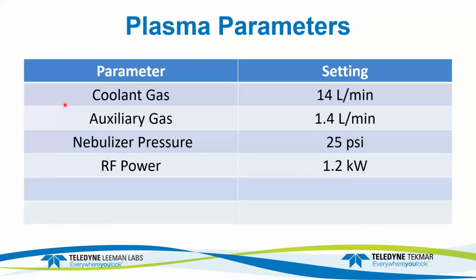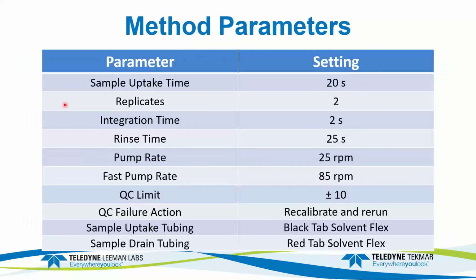So the coolant gas was set to 14, a little bit above the 12 that I talked about earlier. The auxiliary gas, I run a little bit higher. That way I put the torch a little higher in the coil, and I use the auxiliary gas to push the discharge away from the end of the torch. The nebulizer pressure is 25 psi, and that's related to the 1.1 millimeter injector. We can go to a little bit lower pressure, and the RF power, or the forward power, is 1.2 kilowatts, as we said.